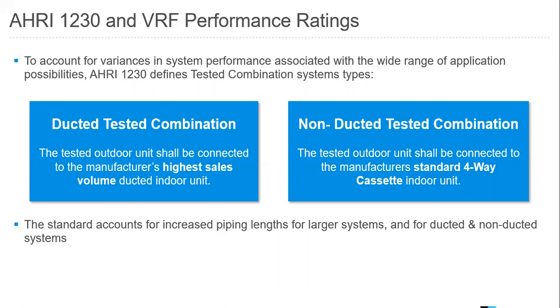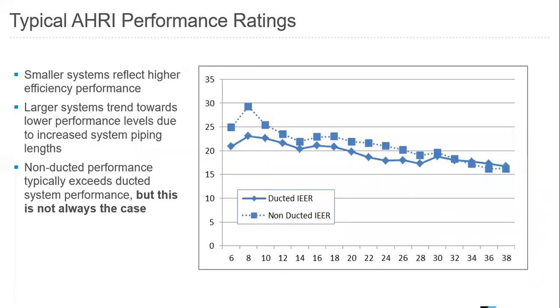And you'll see that the ducted indoor units are actually slightly less efficient than the non-ducted systems. So these systems account for increased piping length for the larger systems as well. Typical AHRI performance ratings, this is kind of what they look like. Like I mentioned earlier, typically the non-ducted indoor units are slightly more efficient. So that's going to be our 4-way cassettes and high wall indoor type units.